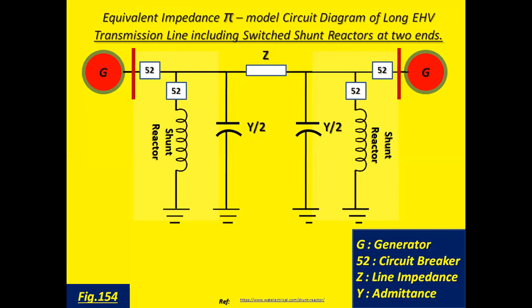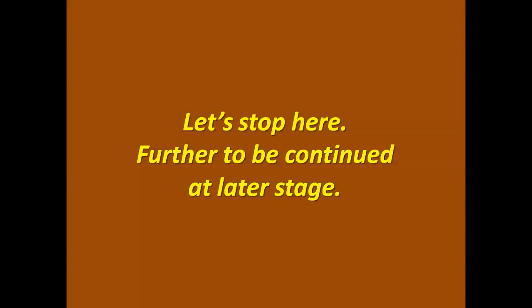See the diagram. Equivalent impedance pi model circuit diagram of a long extra high voltage transmission line, including switched shunt reactors at two ends. Here G is the generator, 52 is the circuit breaker, Z is the line impedance, Y is the admittance. Let's stop here, further to be continued at a later stage.